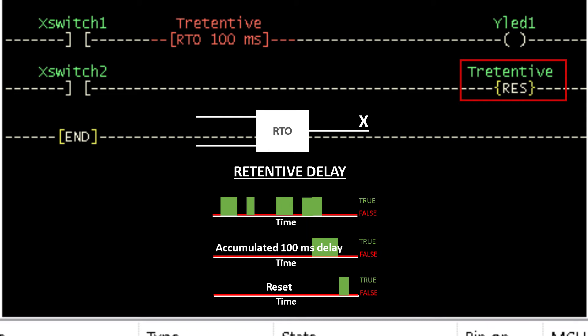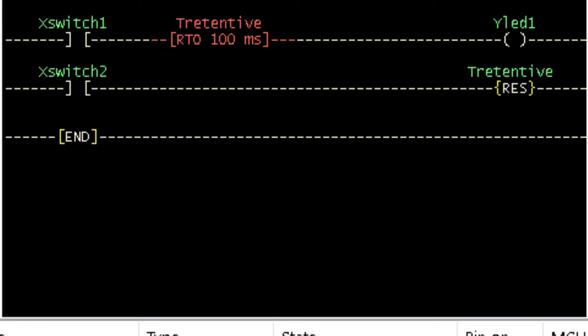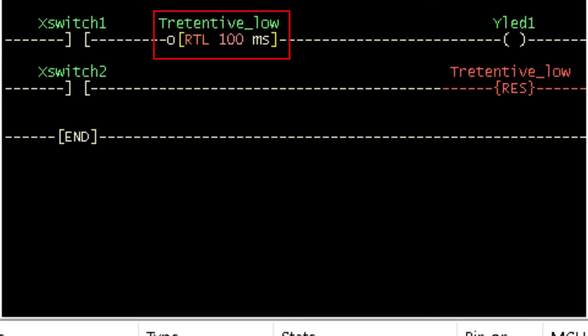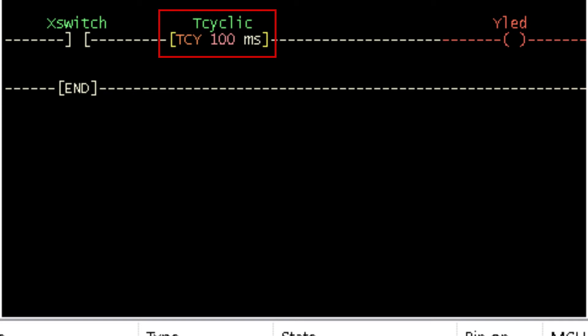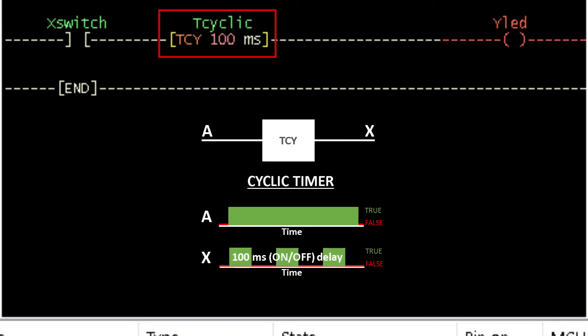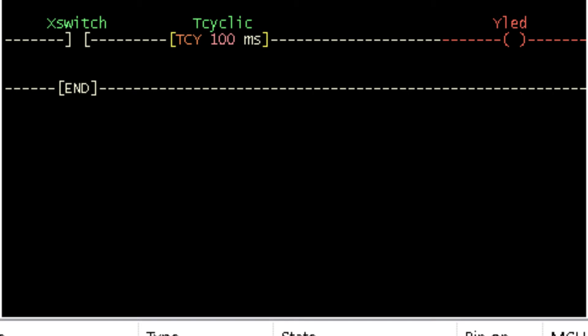The reset instruction from the counter option is used to reset the retentive timer. This timer may be used to write a program that determines the total operating time of a device or equipment. The retentive timer low operates just like the retentive timer but with a low level input. The cyclic timer produces a continuous on-off output. The on time is always equal to the off time as specified in the timer delay. We can also create a program that works like the cyclic timer using turn on delay and turn off delay timers.